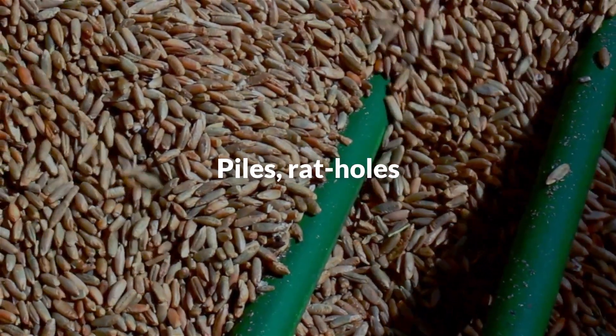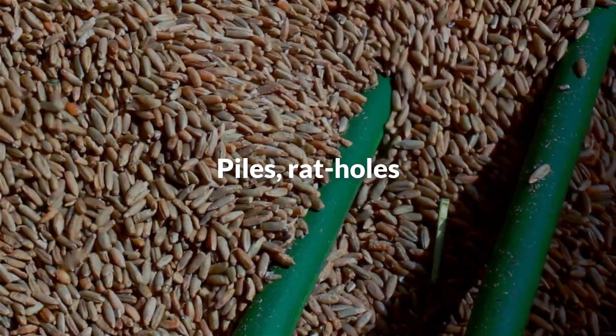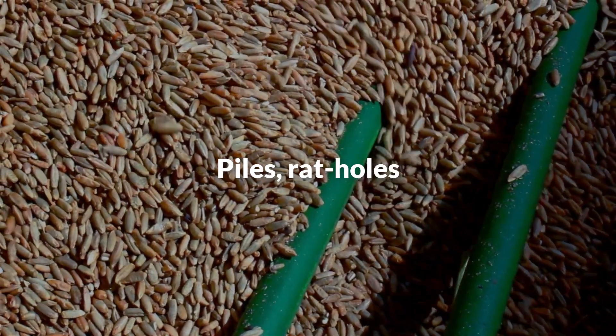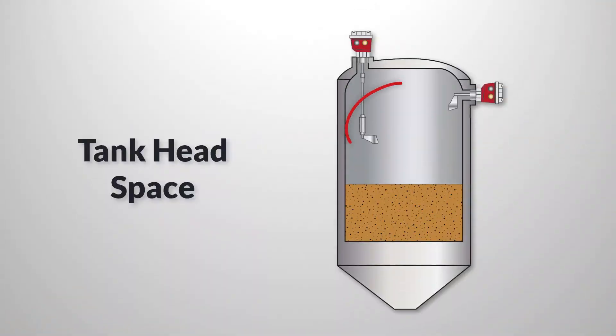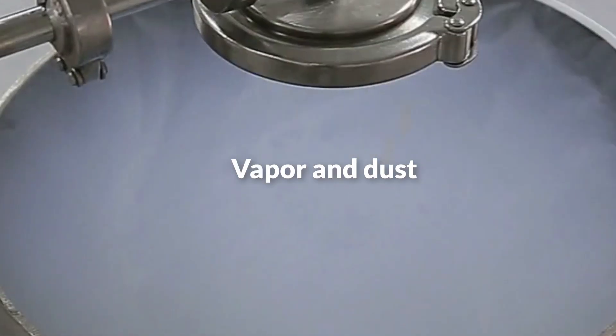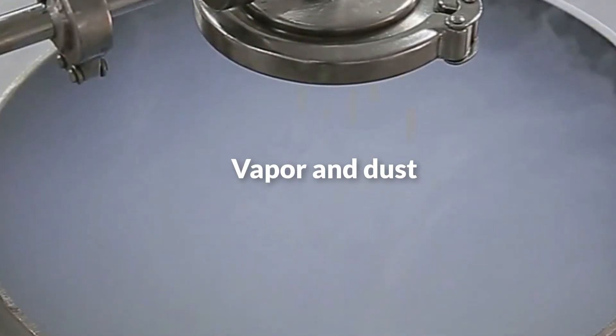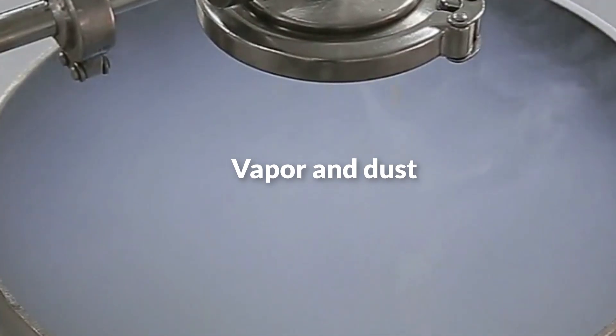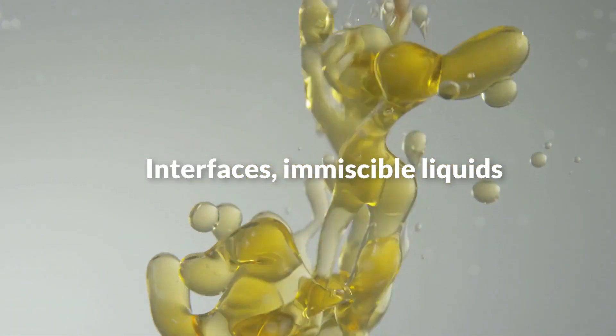If the solids in a silo tend to pile up in one place or form a rat hole, there may be no true level to detect. A tank headspace, the space above the material, may contain vapors or dusts that obscure the view of the surface, and sometimes the level of interest is actually an interface between two immiscible liquids.